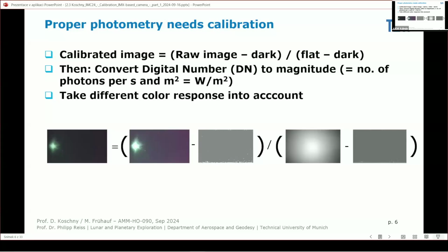So even if you have a completely black image, you know, you cover your camera. I have a black towel that I put over the camera. I switch off the light. We're sitting in the basement and we do it at night. So it's as dark as it can be. And you still get a signal, all right? It's because of temperature that generates electrons in your detector, and that looks like light, which it's not. So you have to subtract that.